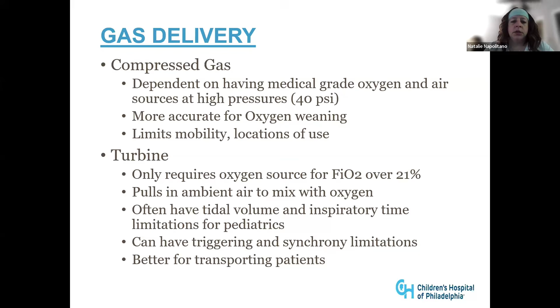Otherwise, you have turbine-driven machines. They only require an oxygen source if you want to have an FiO2 over 21%, but if there's no need for that, if you want to just run off of room air, then you can do that and it will function. It pulls in ambient air to mix with the oxygen to give the desired FiO2. You often have tidal volume and inspiratory time limits, which is a problem for pediatrics. And it's not just that you have a limit of one necessarily, but it's the combination. So to get a lower tidal volume, you need to have a much longer I time, and vice versa. So you can't always get the tidal volume inspiratory time combination that you would necessarily want. They can also have some triggering and synchrony limitations because they're oftentimes not as sensitive because of the mechanics internally. And then it is often better for transporting patients or even for at-home use.